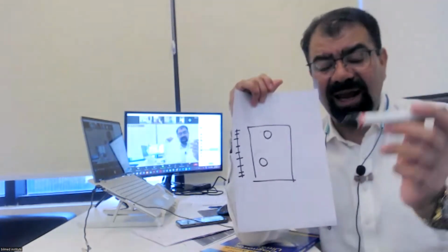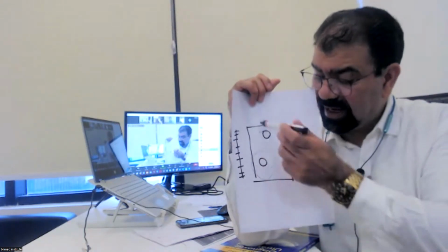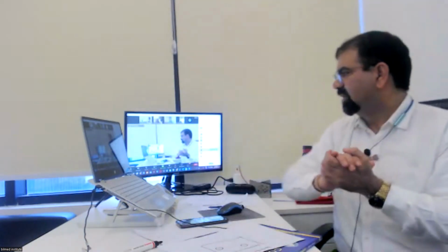So if I have to adjust the gain of a specific area, not the complete monitor, for that is the TGC. I have to check which TGC will work for this. And if I want to adjust the gain of this area, I can do it with the top TGCs. So TGC is nothing but a specific area's gain.